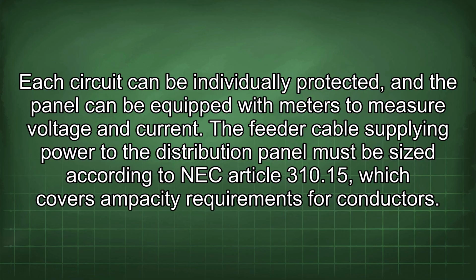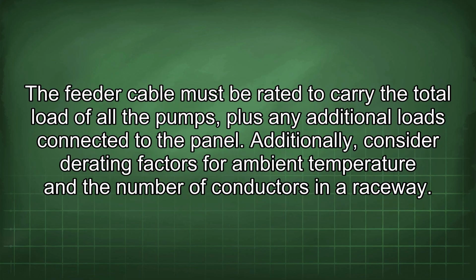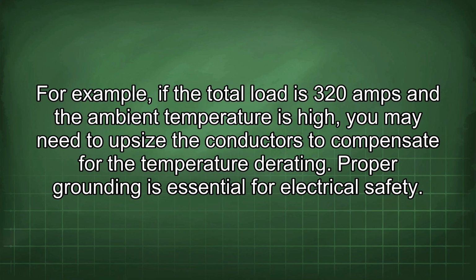A feeder cable supplying power to the distribution panel must be sized according to NEC Article 310.15, which covers ampacity requirements for conductors. The feeder cable must be rated to carry the total load of all the pumps, plus any additional loads connected to the panel. Additionally, consider derating factors for ambient temperature and the number of conductors in a raceway. For example, if the total load is 320 amps and the ambient temperature is high, you may need to upsize the conductors to compensate for the temperature derating.